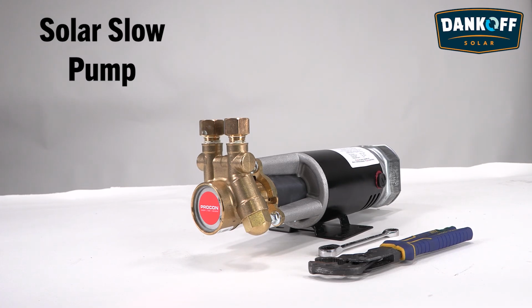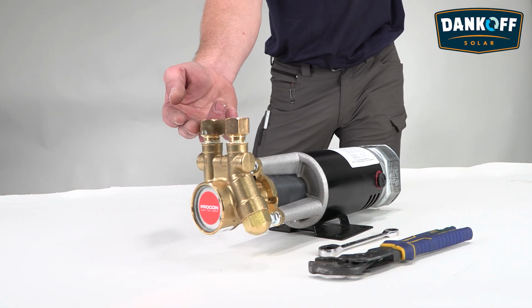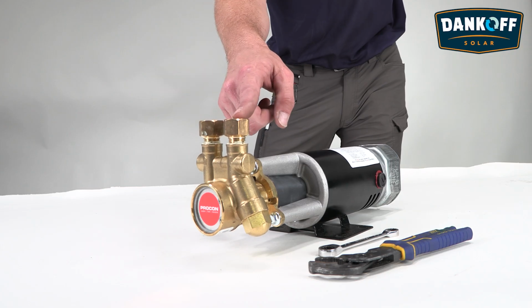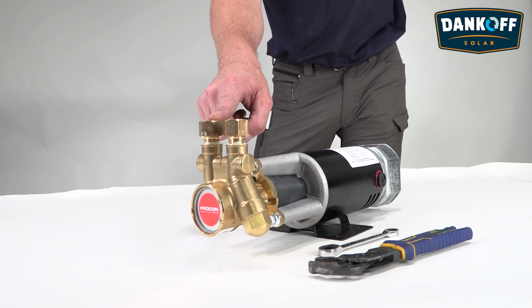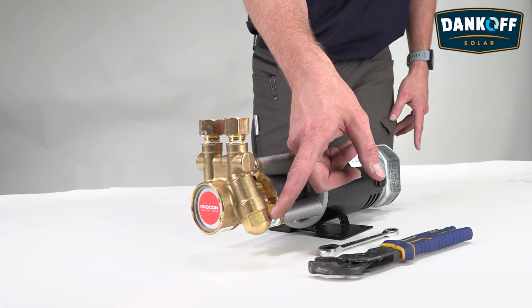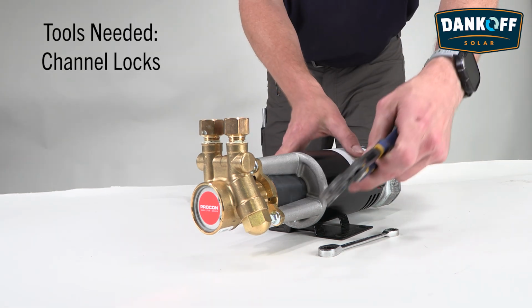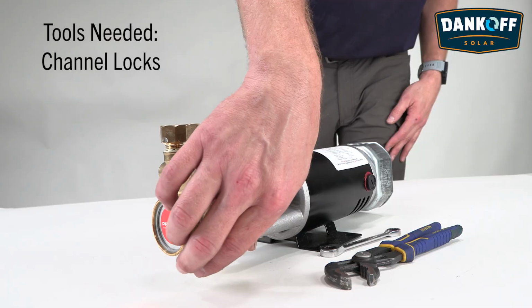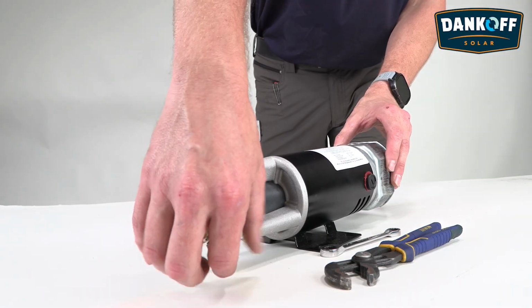This is our 1308 24-volt model. We winterize this pump to avoid cracking in the graphite vanes inside of the pump head. Winterizing these is also a rather simple process. The first step is to disconnect the intake, which would be found here, followed by the discharge line, which would be found here. Next, we will need to remove this hex nut.